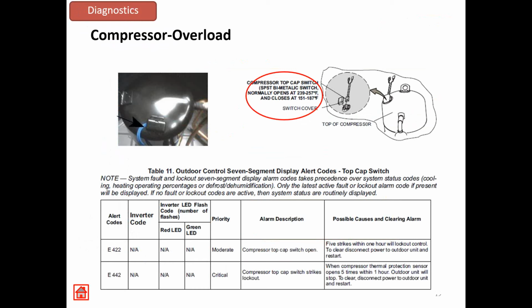Again, we talked about that top cap. This is a 5-strike lockout. If we're getting that hot, we got some issues with refrigerant, something to really pay attention to. Something's going on to cause it, because that's pretty warm on top of that compressor. So the 422 is the code that would open up, and then after 5 strikes, we would go to a 442. And that's some of our codes.